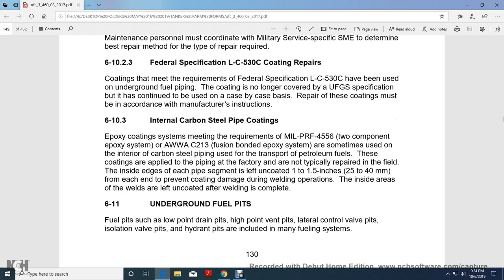610-3, internal carbon steel pipe coating. Epoxy coating systems meeting the requirements of MIL-PRF-4556, two-component epoxy system, or AWWA C213 fusion bonded epoxy system, are sometimes used with the interior of carbon steel piping used to transport fuel petroleum lines. The coatings are applied at the piping factory with no typical field repair. The inside edge of each pipe segment is left uncoated 1 to 1 1/2 inches from each end, preventing coating damage during welding operations. These inside areas of the welds are left uncoated after the welding is completed.